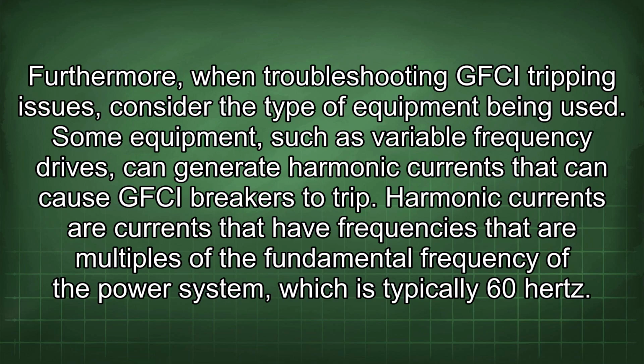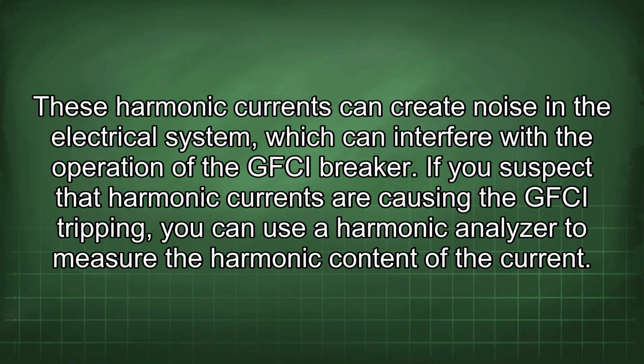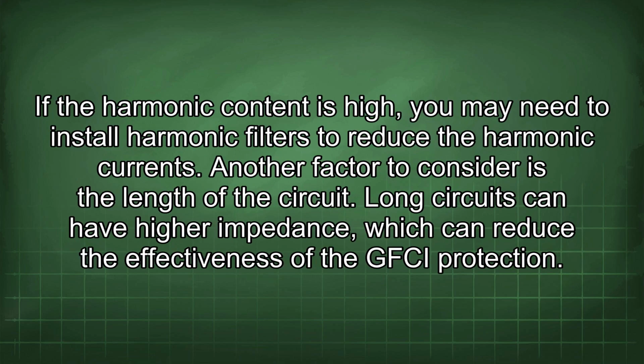Some equipment, such as variable frequency drives, can generate harmonic currents that can cause GFCI breakers to trip. Harmonic currents are currents that have frequencies that are multiples of the fundamental frequency of the power system, which is typically 60 Hz. These harmonic currents can create noise in the electrical system, which can interfere with the operation of the GFCI breaker. If you suspect that harmonic currents are causing the GFCI tripping, you can use a harmonic analyzer to measure the harmonic content of the current. If the harmonic content is high, you may need to install harmonic filters to reduce the harmonic currents.